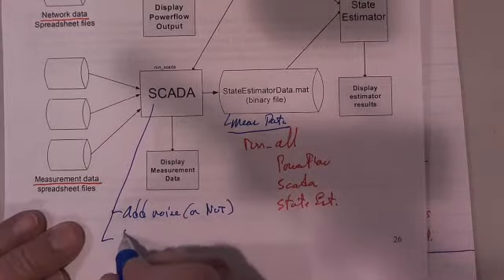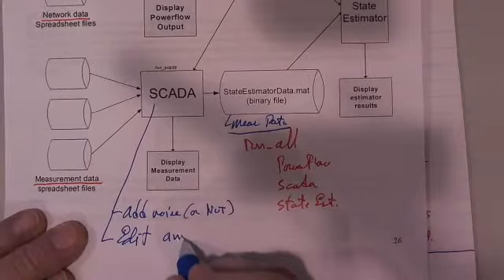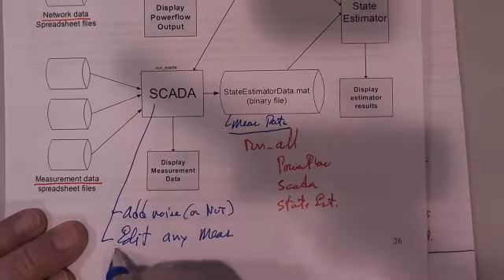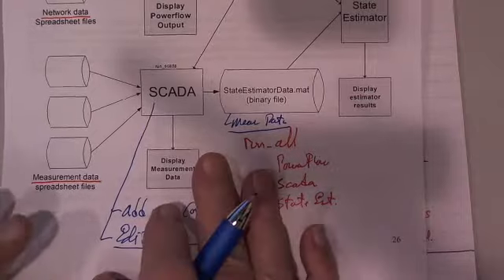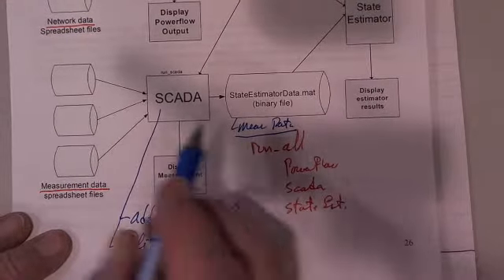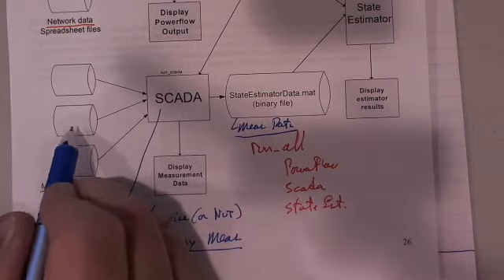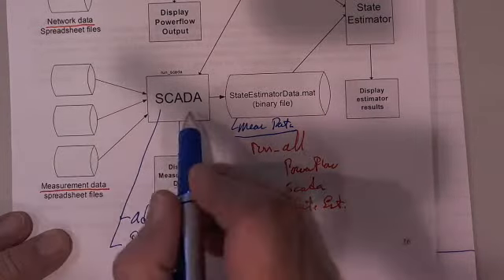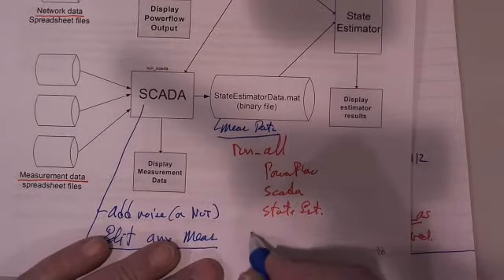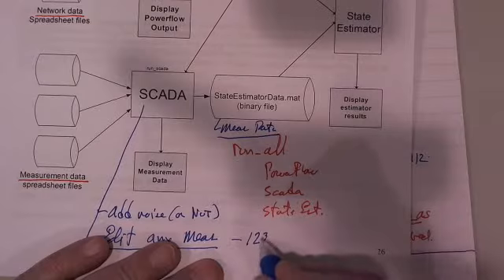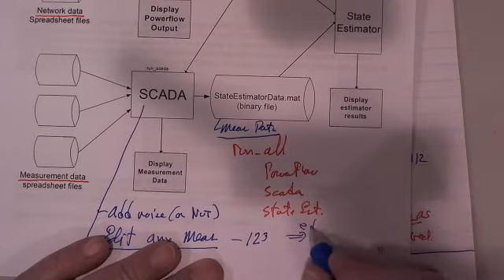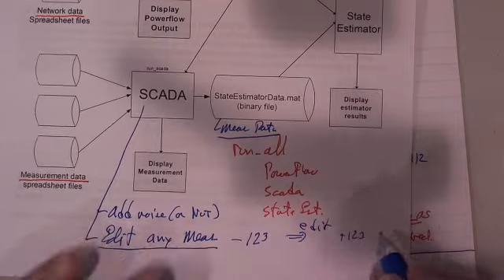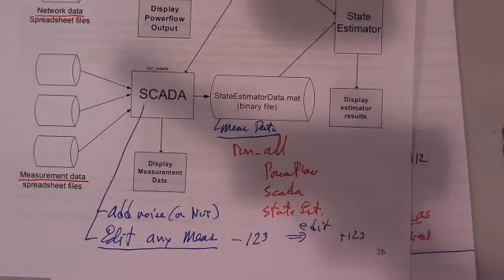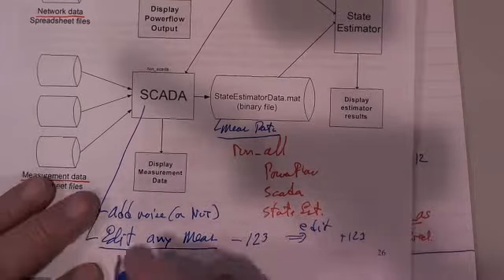I can also edit any measurement. Now if you want to turn a measurement off before the whole process starts, you go back into the spreadsheet file and change its status. But what you can do here is, if this measurement was, say, minus 123, I changed it, edited it to plus 123. The editing is simply a way of testing the state estimator, making some of them bad - so this is really where you make it bad.